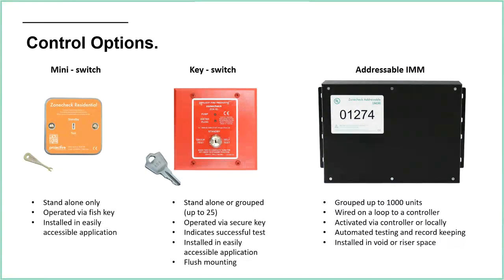The key switch is the same key switch that we use on our commercial zone checks. It has some lights on the front, which give you a little bit of feedback in terms of whether the pump is running, and tell you when the test has been successful. They can also be grouped together in groups of up to 25, so you can do multiple testing at once.